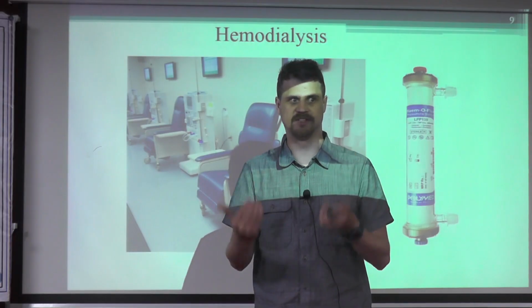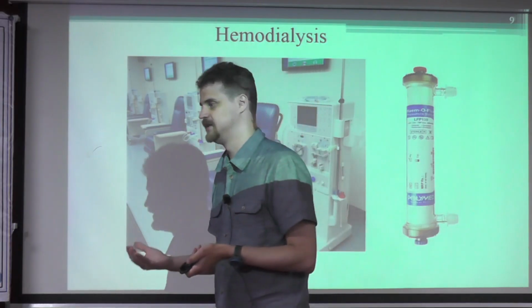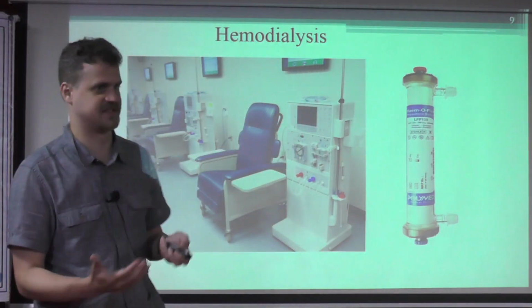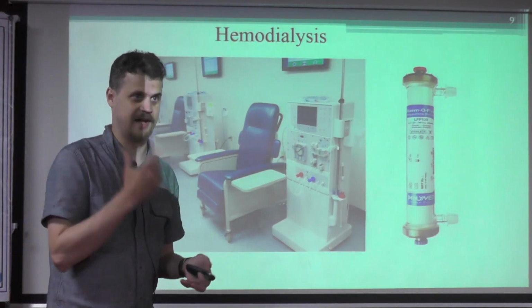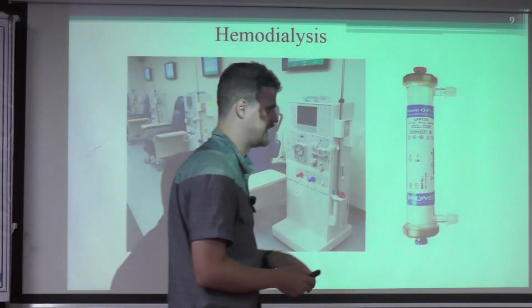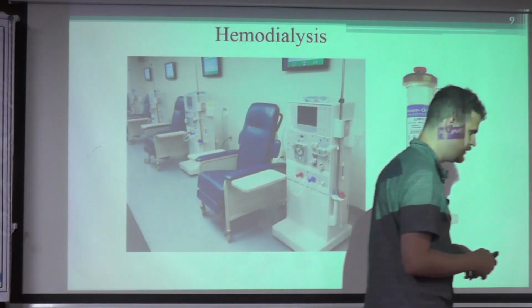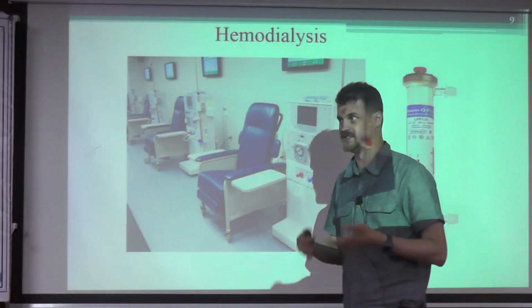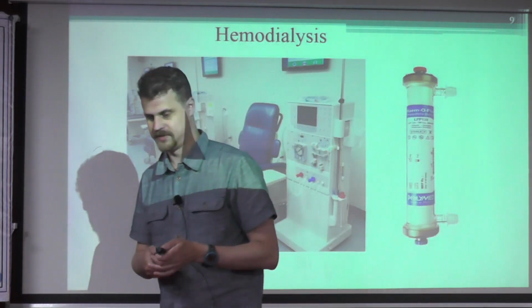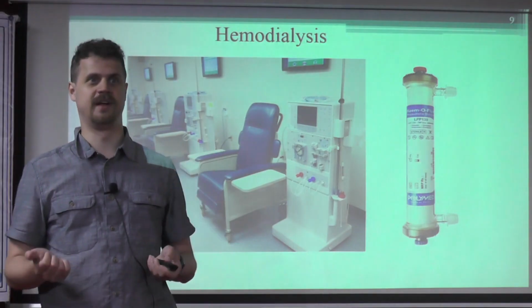So there is a very strict demand for any hemodialysis system in case of what water should be used, and these restrictions are even more strict in case of microorganisms that can be presented in the tap water or anywhere else.